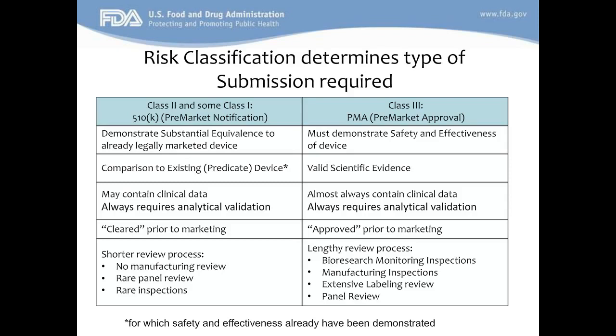As you can imagine, a Class 3 high-risk device requires more valid scientific evidence. It always requires clinical data. It requires a lengthy review process, including manufacturing inspections, whereas a 510K device is cleared by comparison to an existing predicate device. Let's take an example, immunoassays. There are many immunoassays that have been cleared already and are marketed to measure something like rheumatoid factor for rheumatoid arthritis. A new device that measures rheumatoid factor would then be compared to a device that already measures that analyte, and the performance of that device has to be equivalent to the predicate device.